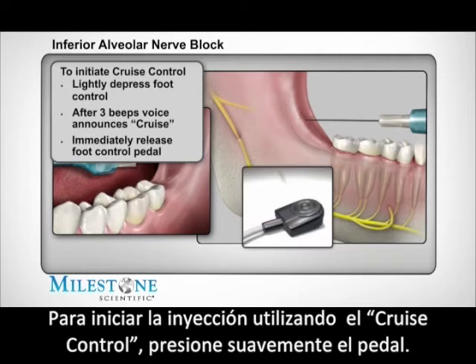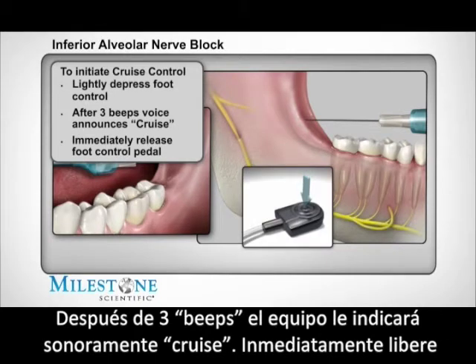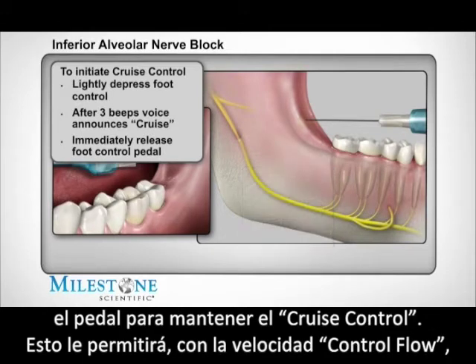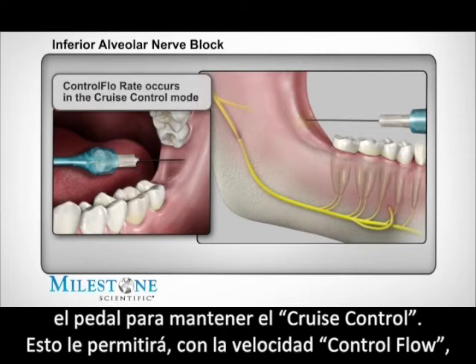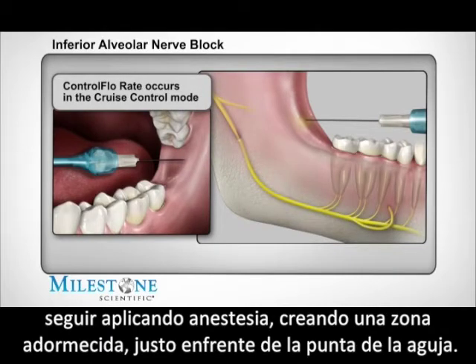To initiate the injection using cruise control, slightly depress the foot control. After three beeps, you will hear the STA system announce 'cruise.' Immediately release the foot control pedal to enter into the cruise control mode. This allows the control flow rate to continue to dispense anesthetic solution, creating an anesthetic zone in front of the tip of the needle.